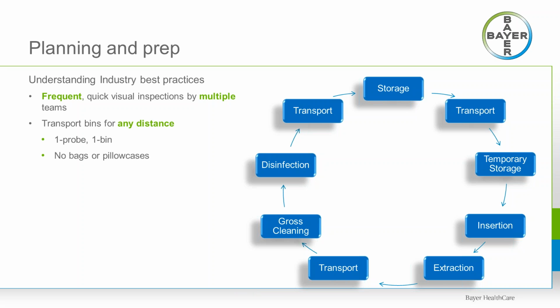Although very popular, do not use bags or pillowcases to transport TEE probes. It's really suggested that you use some type of transport bin or surgical tray for transporting really any length of distance, even if it's from one room to the other. And also use the rule of one probe to one bin or tray. Another important feature is to not stack anything or place anything on top of a TEE probe. Some type of tip protection should remain in place at all times except during insertion. We'll talk a little bit about that in a few minutes.